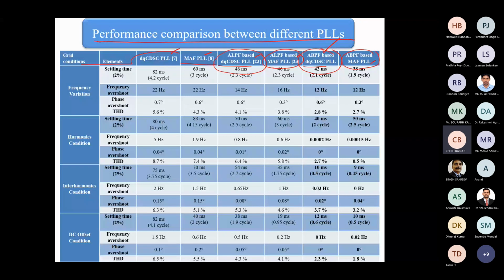This is the performance of the proposed PLL. These PLLs can be added as a pre-filter for any kind of PLL, and we see the comparison for different power quality scenarios, including frequency variation, high frequency harmonic injection, interharmonics presence in the utility grid, and DC offset current injected into the utility grid. Overall, the performance is very superior.